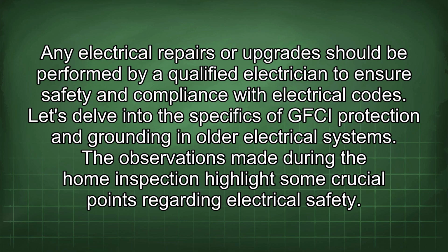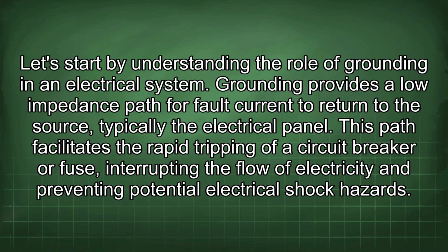The observations made during the home inspection highlight some crucial points regarding electrical safety. Let's start by understanding the role of grounding in an electrical system. Grounding provides a low impedance path for fault current to return to the source, typically the electrical panel.